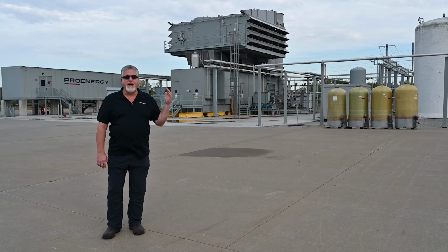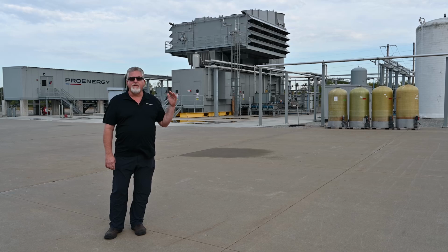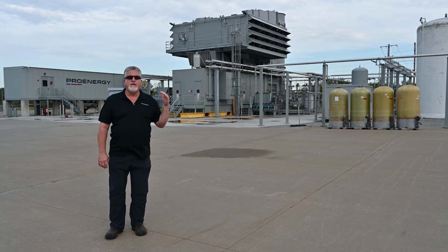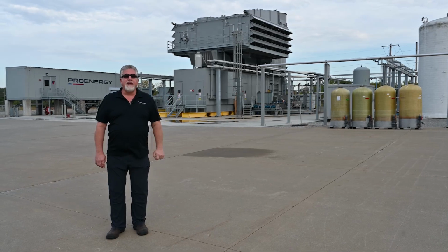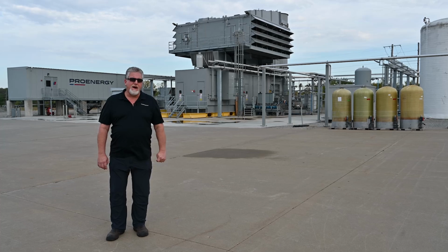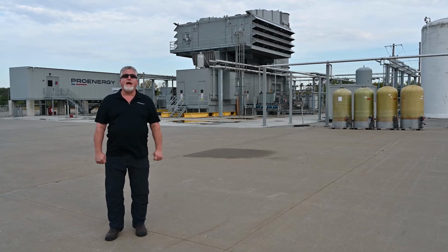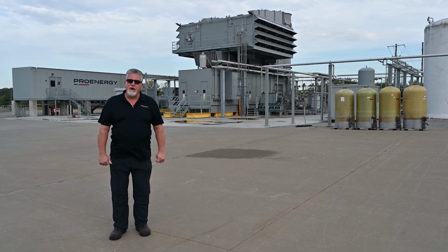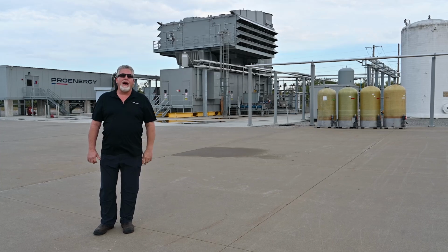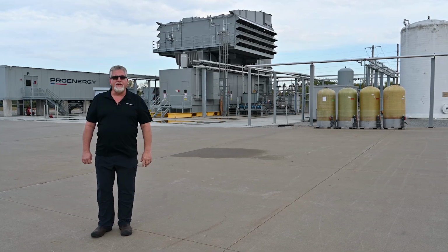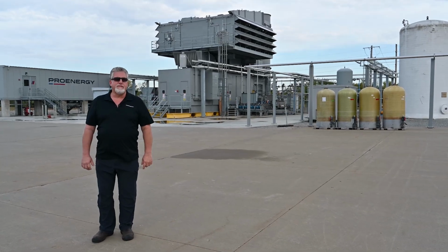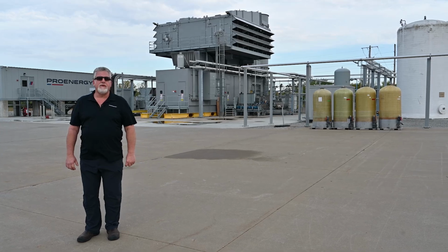In front of the turbine package is the generator. This generator is a 65 megawatt, 13.6 kilovolt AC generator. We take this power and dissipate it on a 65 megawatt load bank so that we can control how long and as fast as we need to be on point for performance and new production testing.